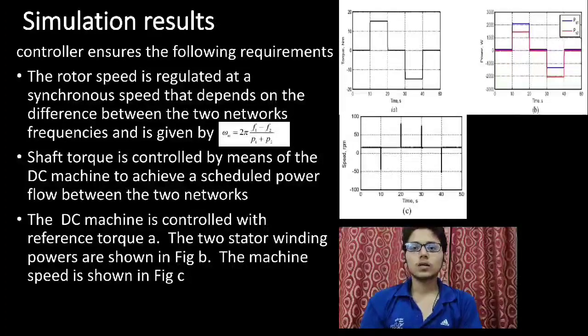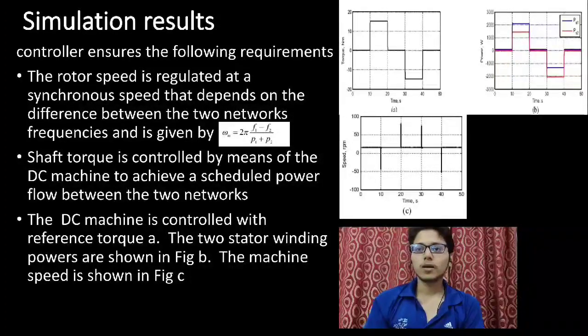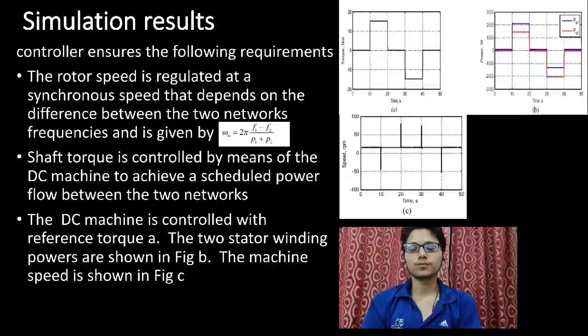First, the rotor speed is regulated at the synchronous speed that depends on the difference between the two network frequencies. And second, the shaft torque is controlled by means of a DC machine to achieve a scheduled power flow between the two networks.